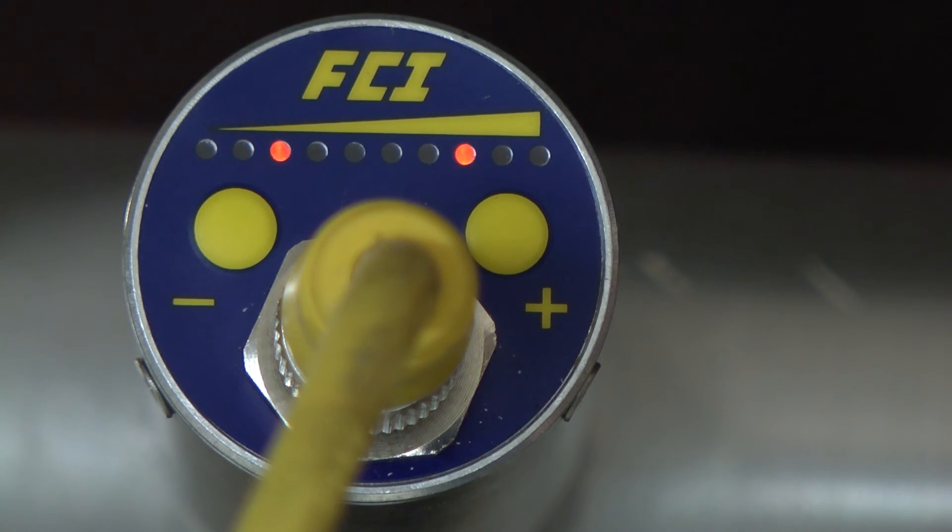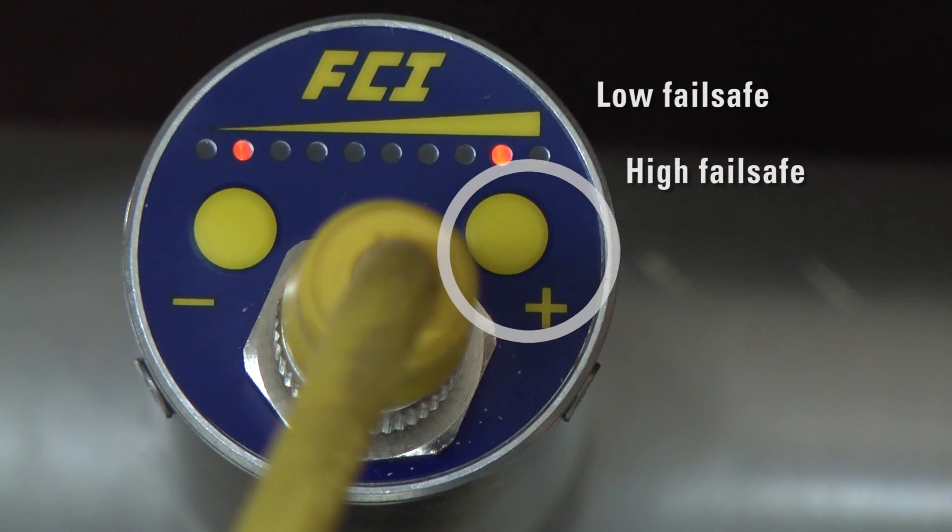As described earlier, momentarily press the minus button to exit with a fail-safe low—that is, relay de-energized in the alarm state—or the plus button for fail-safe high—that is, relay de-energized above the trip point.